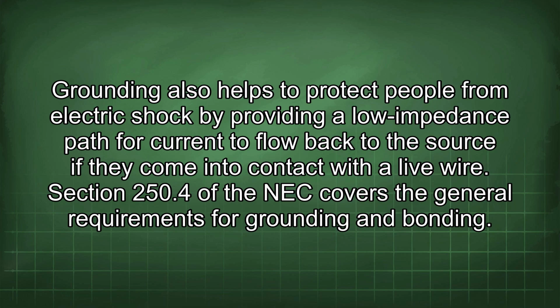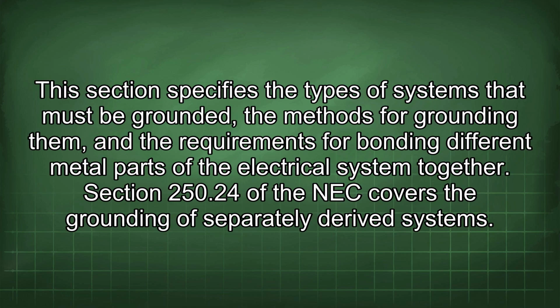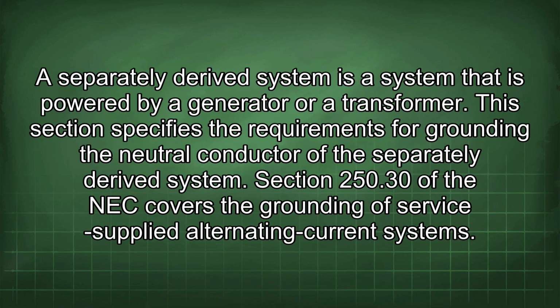Section 250.4 of the NEC covers the general requirements for grounding and bonding. This section specifies the types of systems that must be grounded, the methods for grounding them, and the requirements for bonding different metal parts of the electrical system together. Section 250.24 of the NEC covers the grounding of separately derived systems. A separately derived system is a system that is powered by a generator or a transformer.